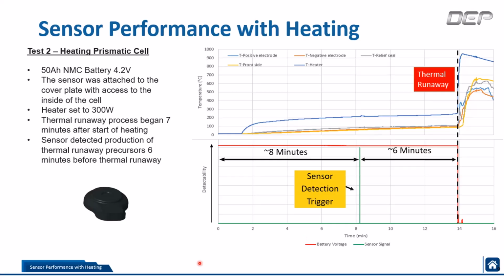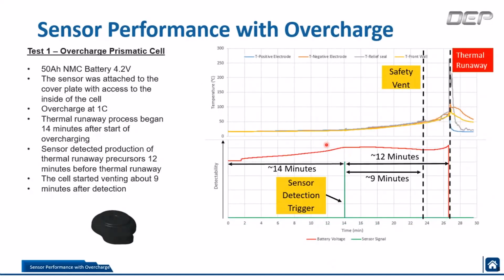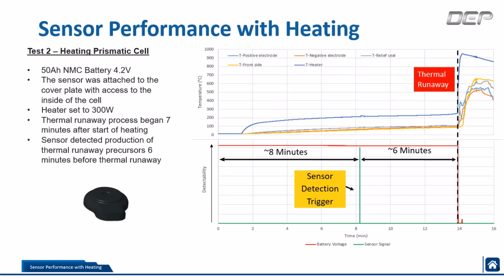In the previous test, however, even though the voltage ran up to where it could hit maximum, the temperature did not go anywhere above 30 degrees. So independent of the temperature and voltage, our sensor is able to detect that thermal runaway.